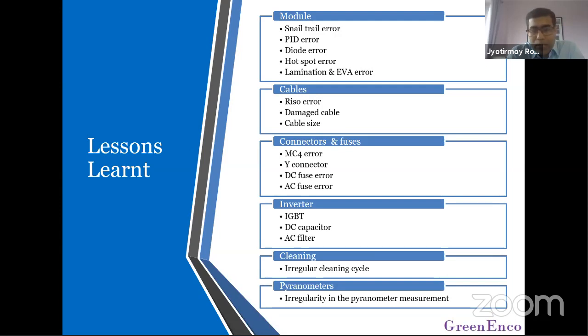Another category commonly seen across different geographies is cable issues. One topic I'd like to highlight is cable sizing. In the past, looking at the seasonal pattern of a particular site with a central inverter, we observed that in some combiner boxes, some strings were underperforming during summertime when irradiance was high, but not during winter when irradiance was low. We did a cable sizing calculation ourselves and found that the underperforming strings during high irradiance days had undersized cable, nearly 50%. So purely by looking at the seasonal pattern of the data, we were able to identify a plant issue with some of the cables.